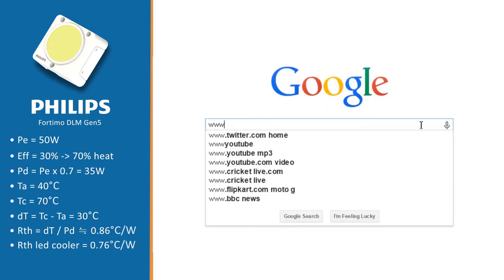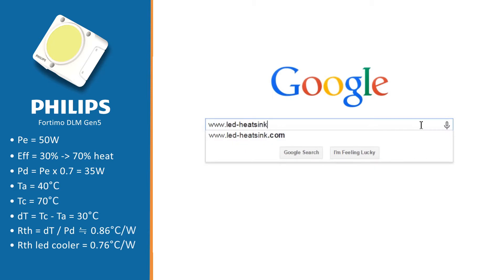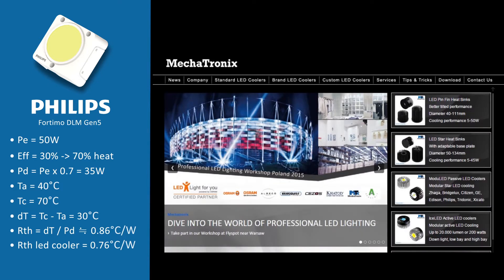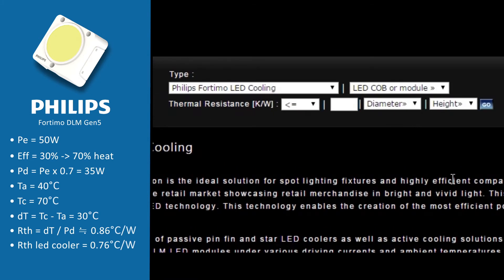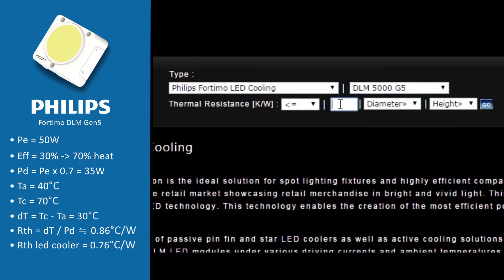We now go to our website, www.led-heatsink.com, and we go to the section of Philips. On the top right side, we first select our LED module — that was the Fortimo DLM5000. Then we fill out our calculated value of the thermal resistance, 0.76 degrees Celsius per watt, and we click on go.